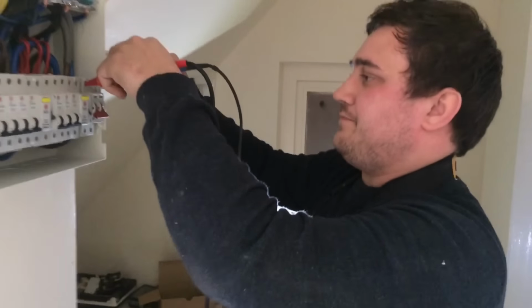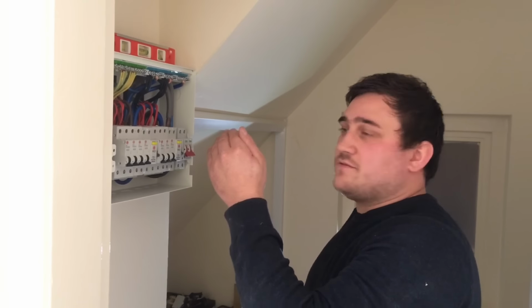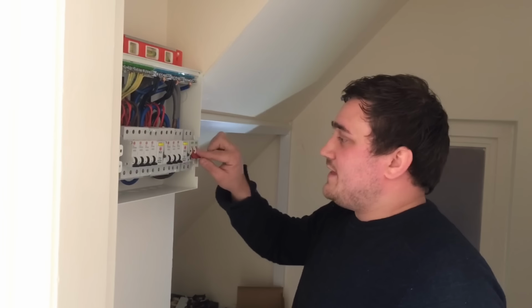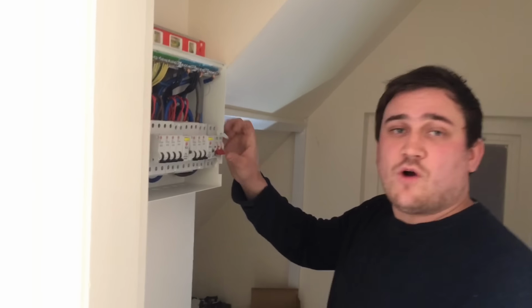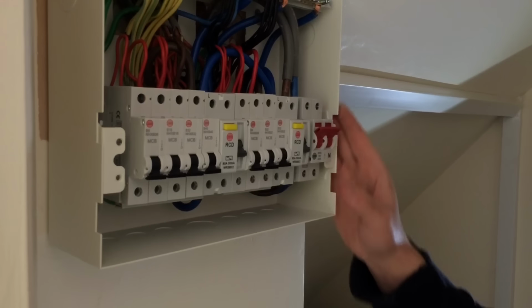0.507 amps. So we take the worst case scenario for them, which was the 1.2 kiloamps, so that will be our PFC for the main incoming fuse. We're now going to check our PFC for the top of the breakers. So for that we need to energise the circuits, and we're doing this so there's no loads on while we energise the main switch. So as you can see, everything is off, and then one by one.